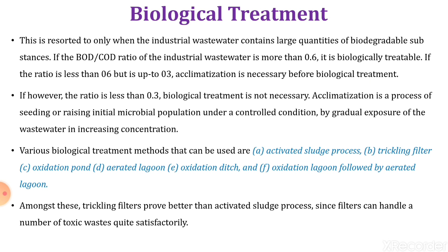If the BOD/COD ratio of the industrial water is more than 0.6, it is biologically treatable. This ratio is also called the treatability index. If the BOD/COD ratio is greater than 0.6, it is a direct indication that biodegradable matter is more predominant in the wastewater, and biological treatment is recommended.